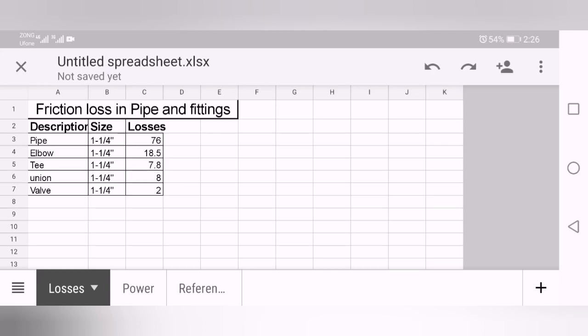How much power do you require to pump a liquid from one place to another? In pump calculation you just need three things: one, the flow rate; second, the specific gravity of the liquid you are dealing with; and third, the total dynamic head. These three things are the most important.